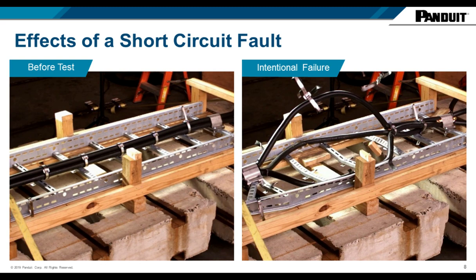After the intentional failure test, you can see where the cables have flown out of the cable tray, breaking the cleats and damaging the cable tray, as well as potentially damaging anything near this equipment in the facility.